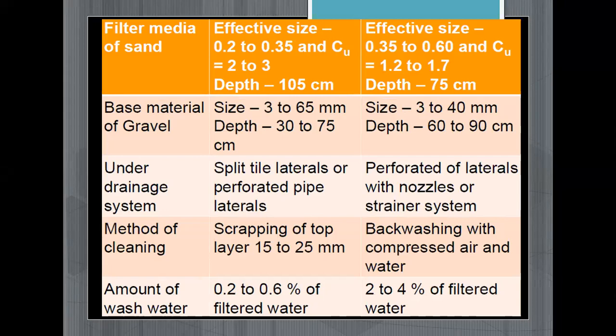The next point of comparison is the filter media of sand — effective size. The effective size of the sand is small in the case of the slow sand filter, while in the rapid sand filter the sand size is somewhat larger; coarser sand is used. Then the depth of the sand media: in the slow sand filter it is 105 cm, but in the rapid sand filter the depth is up to 75 cm.